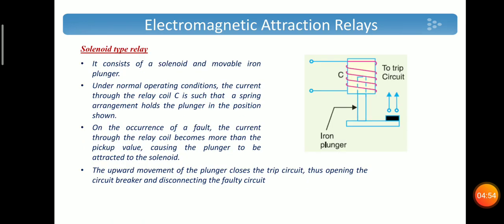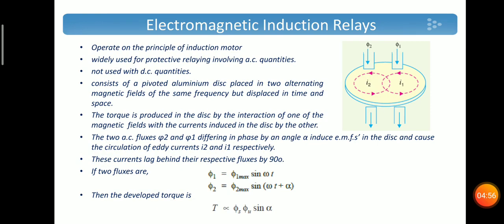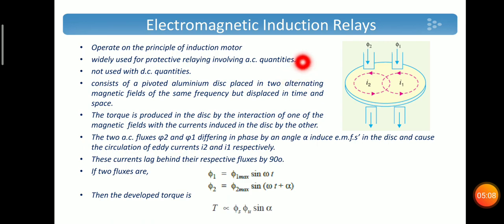Those three are electromagnetic attraction type relays. Next is electromagnetic induction relays. The principle is similar to that of an induction motor. It is widely used for measuring or for protecting AC systems — it cannot be used with DC quantities. It consists of a pivoted aluminum disc between two alternating magnetic fields phi-1 and phi-2.